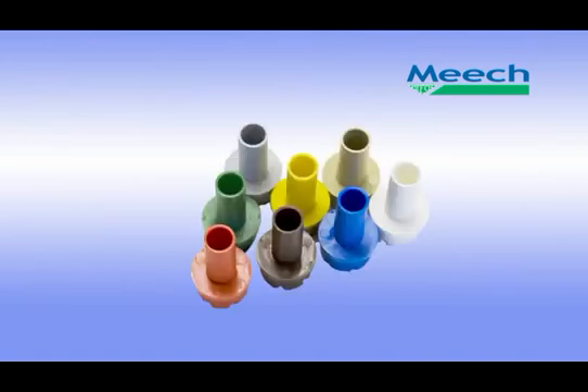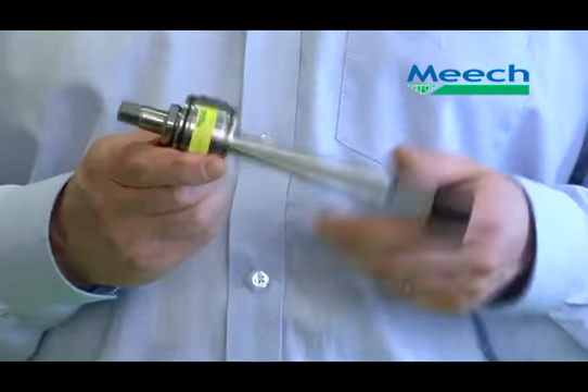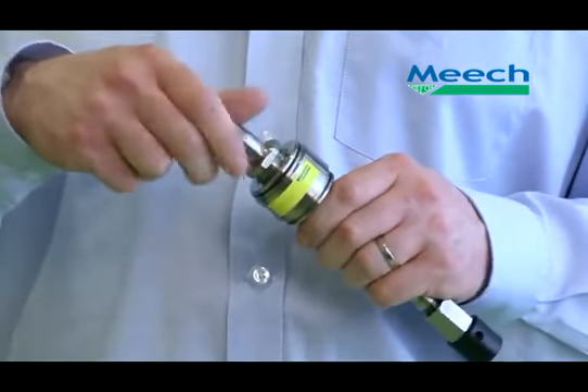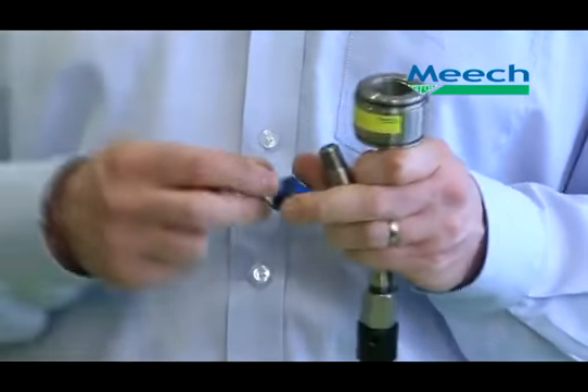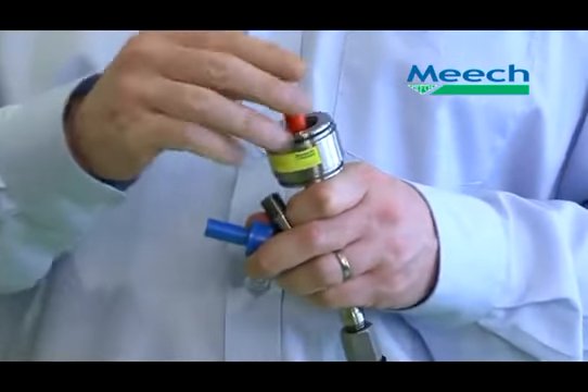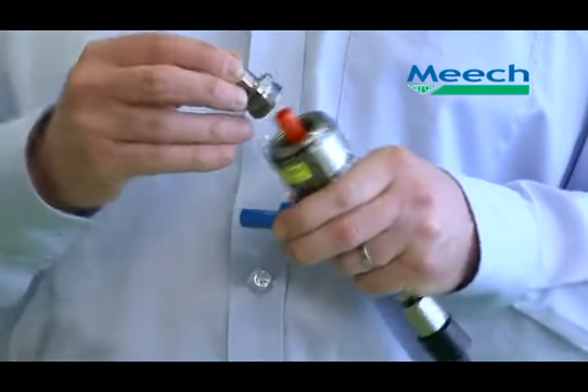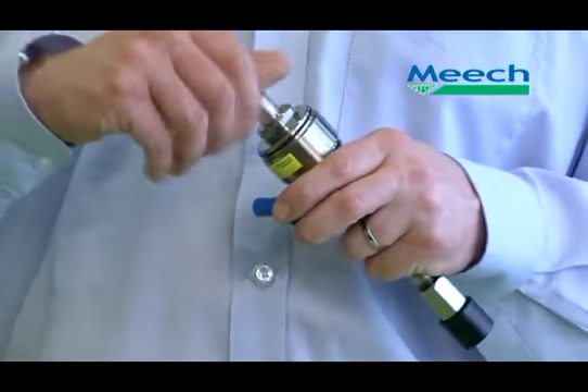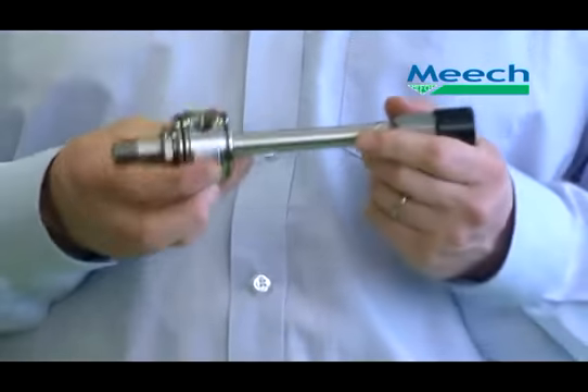The second way to control the air temperature and flow is through the generator used within the vortex. The generators control the air consumption and influence the achievable temperatures. 8 generators are available for the medium vortex tubes, 4 with a high cold fraction and 4 with a low cold fraction. Each generator will achieve a different airflow and temperature range. The 8 generators offer 4 different air consumptions: 10, 15, 25 and 35 CFM. Generators can be changed according to the application needs. As shown, this can be done quickly and relatively easily.